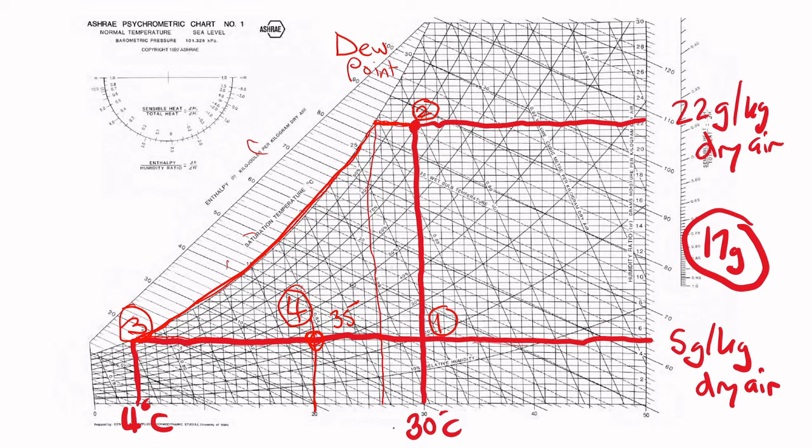In other cases, I have some plants I work with where they're running this dehydration cycle, but then they're bringing it back up to, let's say, ambient at 20 degrees in the summertime. Now with the relative humidity, it's pushing like 35%. This is common in a lot of high precision food processing, such as the cannabis market producing cannabis edibles products. They want to treat it almost like a pharmaceutical environment where the relative humidity is very tightly controlled. You can go and rewarm that air, and now the relative humidity is extremely low. Using a dehumidifier which is cooling the air, dropping the water out and then rewarming can be beneficial in terms of modifying your relative humidity.